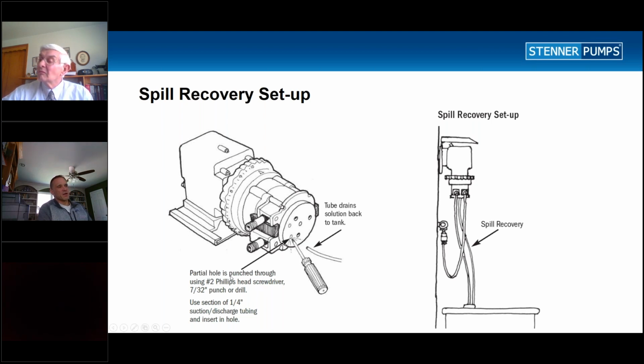Well, you can punch it out with a 7/32 punch or 1/4 inch number 2 Phillips head screwdriver. In my case, just so that it's easy to take care of it and get the tube in there correctly, I'd recommend just taking your 7/32 drill and just drilling out the hole. What that'll allow you to do is attach a 1/4 inch discharge line that can just then be used as spill recovery. So if the tube does break, it's not going to flood the pump housing chamber. It'll give fluids a place to go.